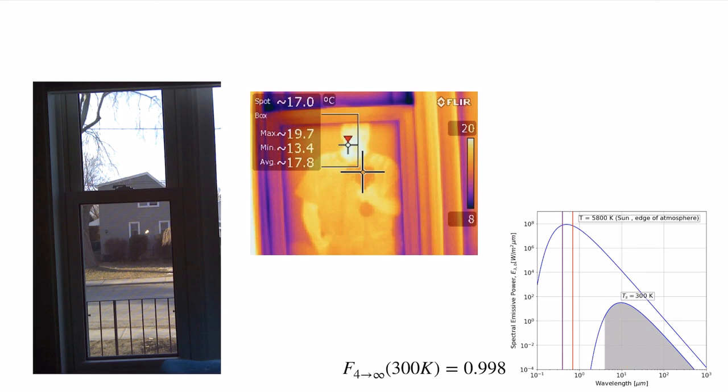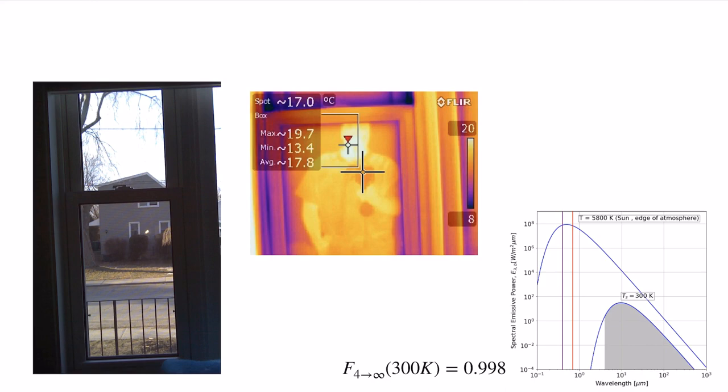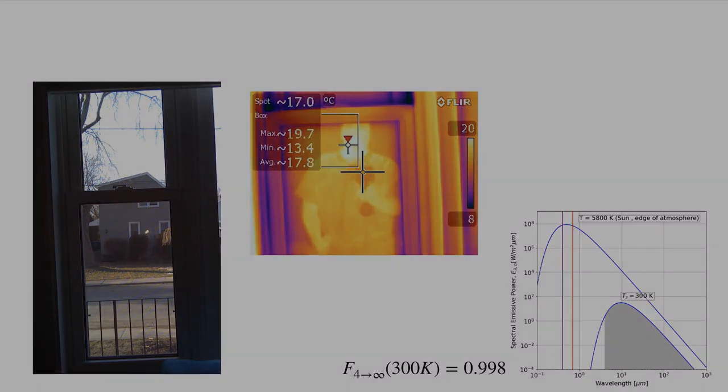Even at four microns, which is the higher end of where the transmissivity drops off for most glasses, 99.8% of the energy is still at a value where the window is no longer transparent. The thermal camera sees that window as a perfect mirror. It's perfectly opaque, reflecting all of that back. You're seeing my reflection in that window instead of through. Whereas in the visible, the transmissivity is very high. The visible part of the spectrum goes right through that window, and that's why we use it as a window.